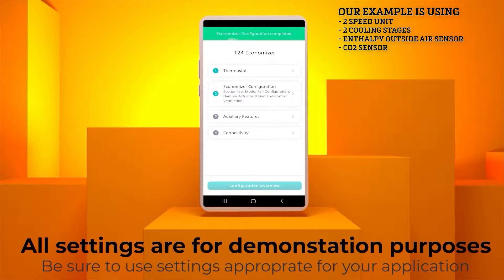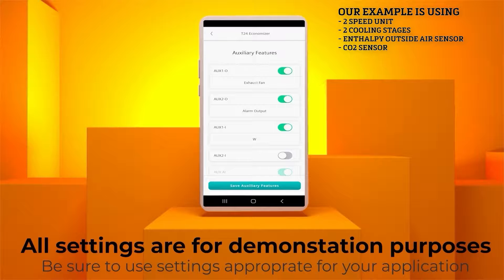Click Finish Economizer Configuration. That will take you to the Auxiliary Features menu. The top tab is AUX1-O, which has a default setting for exhaust fan in the case of a power exhaust fan being used. In our example, we don't have a power exhaust fan. But leaving this setting at exhaust fan even when one is not being used will not cause any faults or system failures. Therefore, it can always be left on.